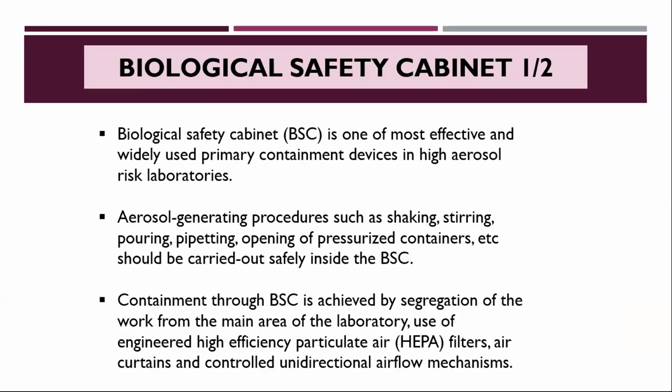Then these are some equipment which we use in the labs, like the biosafety cabinet. It is one of the most effective and widely used primary containment devices, and we use it while doing procedures like shaking, stirring, pipetting, opening of containers. Containment in biosafety cabinets is achieved by segregation of work, and there are high efficiency particulate air filters, HEPA filters, fitted in biosafety cabinets. Air curtains are there, and there is a controlled unidirectional airflow mechanism inside the cabinet.